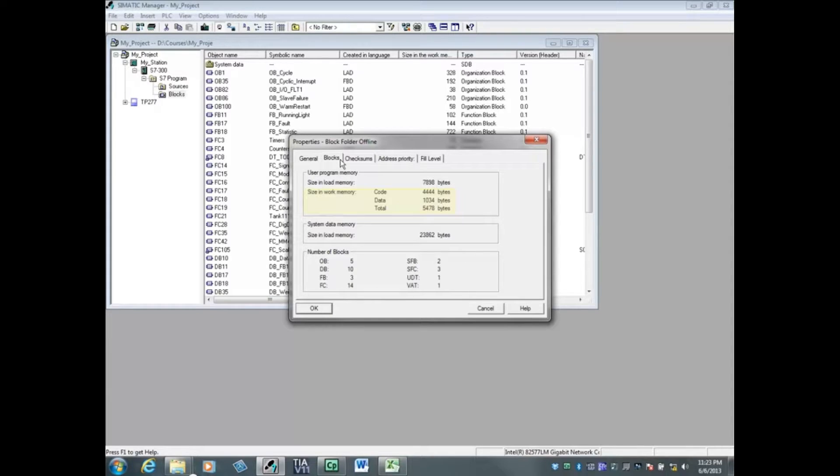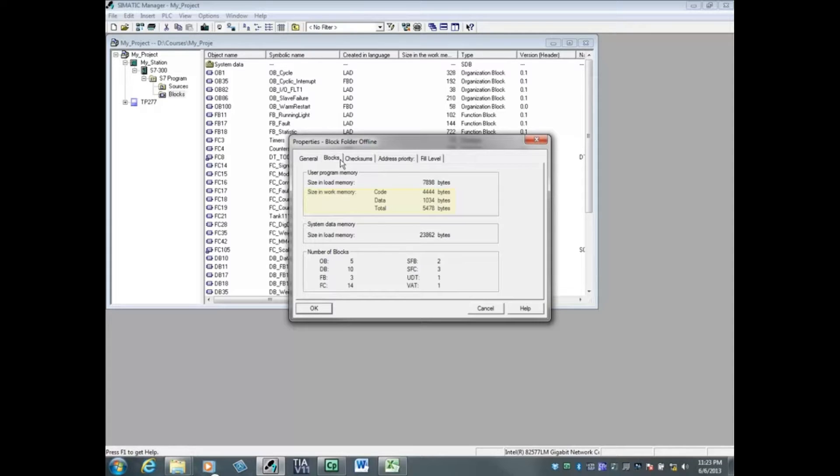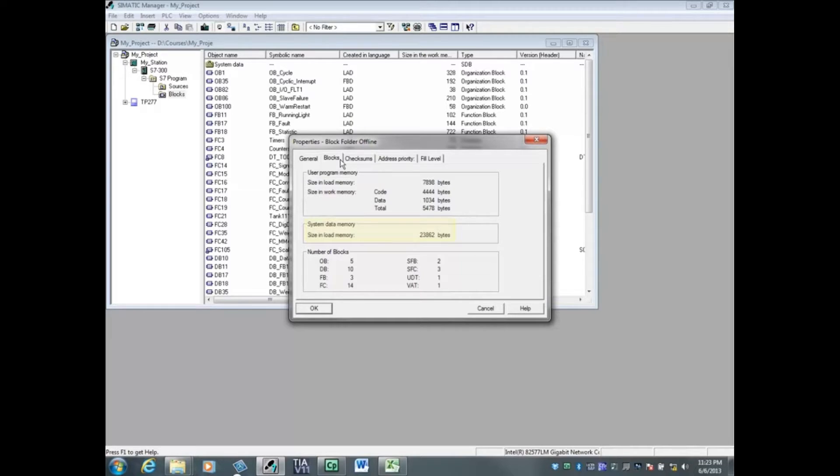In this case, the work memory is 5,478 bytes. The system data memory, 23,862 bytes, is the hardware configuration data and also gets downloaded to the micro memory card.